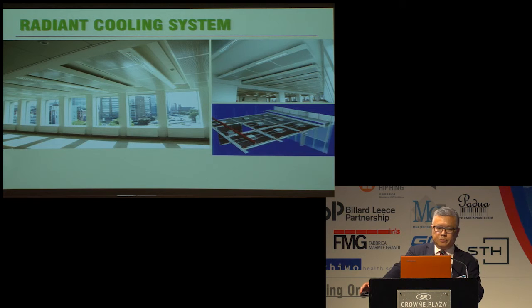Radiant cooling systems with displacement ventilation have been used for hospital projects overseas. The system actually provides draft-free air conditioning, reduces airborne transmitted contaminants, and is highly energy efficient. It also requires less ceiling space for installation. Radiant cooling systems were not used in Hong Kong in the past because under the very high humidity weather in summer, we run the risk of condensation in the air-conditioned space. But situations have changed. In recent years, several radiant cooling systems have been used for offices very successfully and achieved superior energy saving. Perhaps it is time for us to explore the use of radiant cooling in our hospitals.